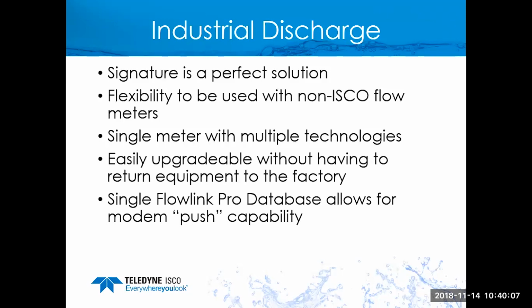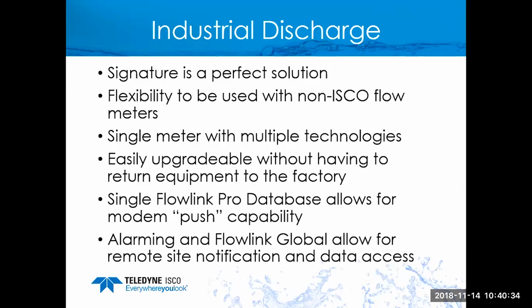Well, now they decided to go ahead and capitalize on that, so they're using signature flow meters on their industry, which allows the industry to be consistent. So they have one platform, but they can modify it as they need. They have a flume that's working, great. They put an ultrasonic signature in and a modem, and it transmits data now to the city's database. So the industry doesn't have to worry about anything. But the other neat thing about this is they can get immediate alarming and notification if there is a problem at the industrial site. So these guys can see, I have an alarm condition. They get it on their phone, they pull up FlowLink Global, and they can immediately see what's happening.